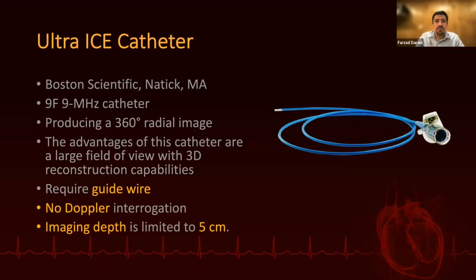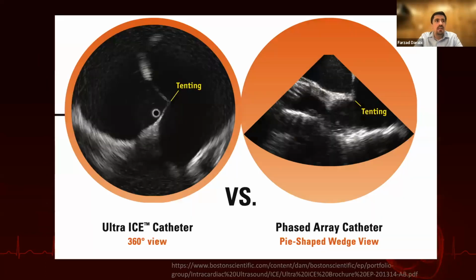Another probe used in ICE, developed by Boston Scientific, is the UltraICE catheter, which is different from the other catheters. This catheter produces a 360-degree radial image. It has the advantage of a huge field of view with 3D reconstruction capabilities, but the disadvantage is that this catheter requires a guide wire, doesn't have Doppler, and the image depth is only 5 centimeters. As you can see, there is a comparison between the longitudinal 90-degree sector probe image that we can see in phased array catheters, in TEE, TTE, and ICE, compared with the 360-degree view of the UltraICE catheter. The catheter is in the middle of the image here, and these are the surrounding structures in the heart.